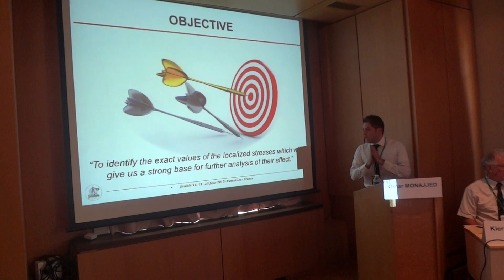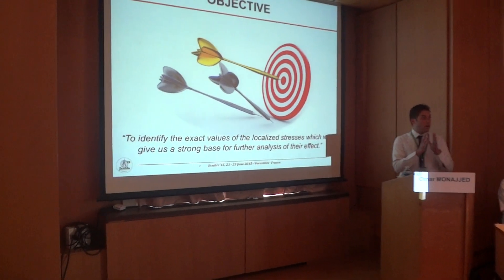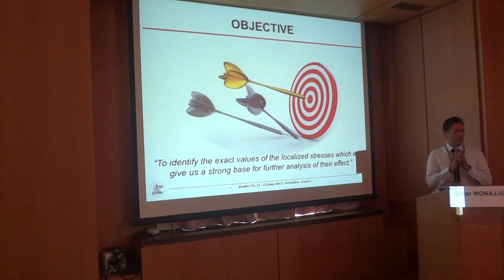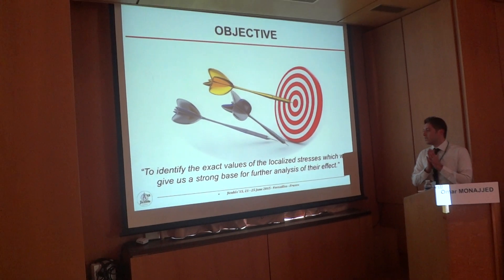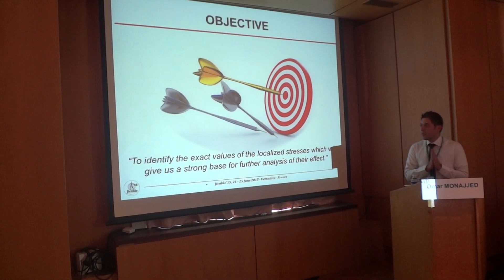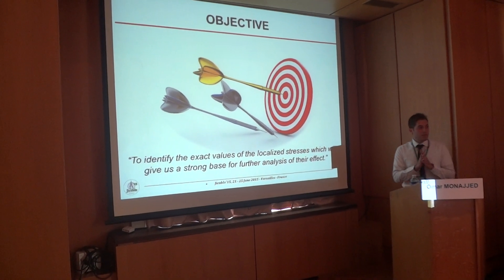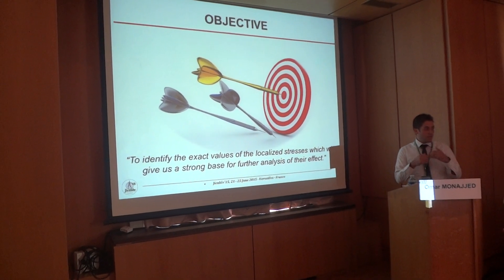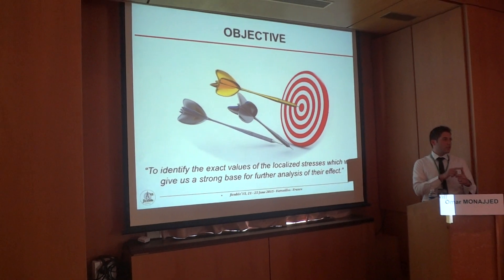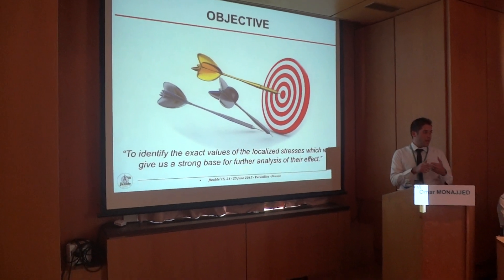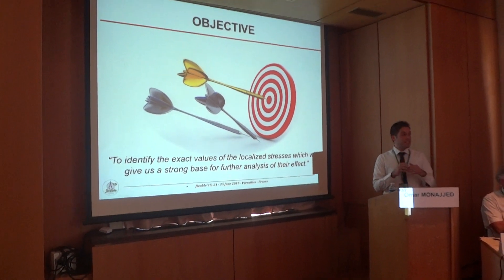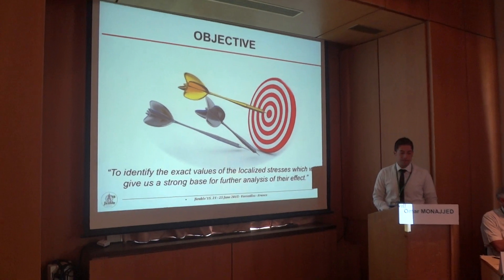The objective of this presentation is to accurately identify and quantify the exact level of the localized enhanced electric stresses caused by these contaminating impurities. Then we can proceed to further analyze the effect on insulation performance by partial discharge, water treeing, and so on. But without this knowledge, we can only make speculations about the situation.